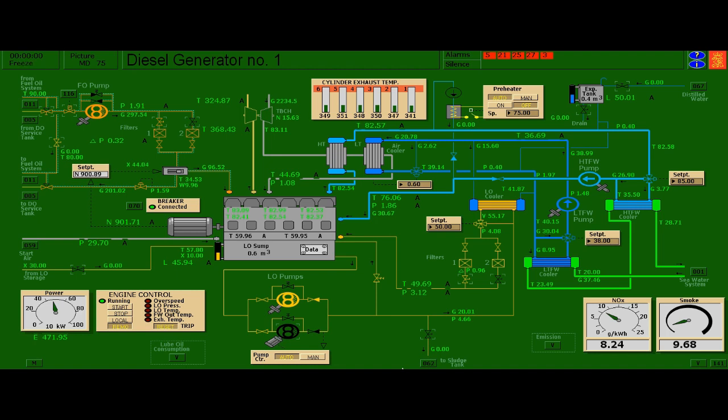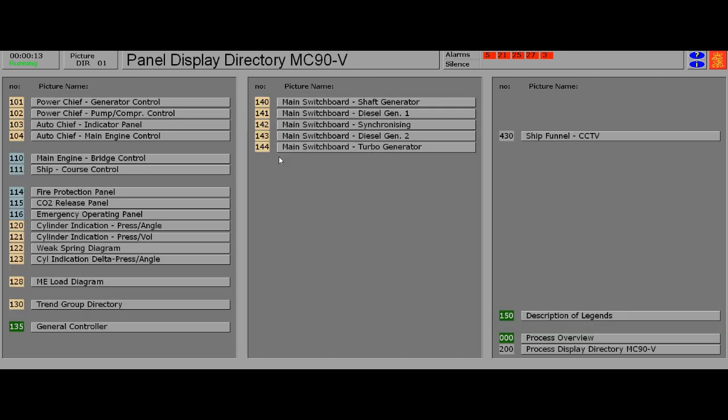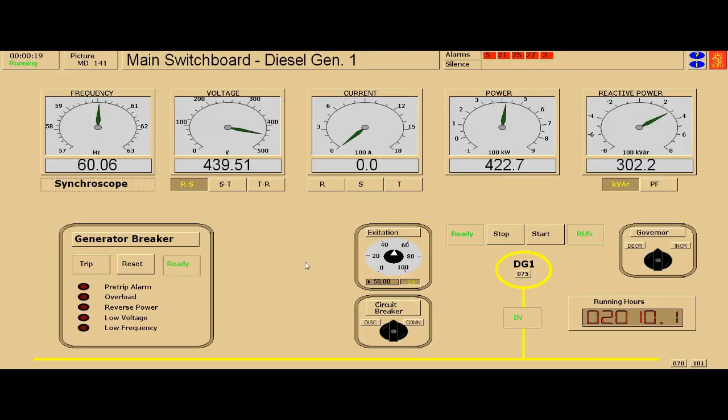As we can see here, the speed of our diesel generator one is around 900 RPM. Let us now check the frequency of the generated voltage. The voltage of this generator is around 440 volts with 60 hertz frequency as shown in the frequency meter. Let us now increase the frequency of this generator and observe the changes in RPM.